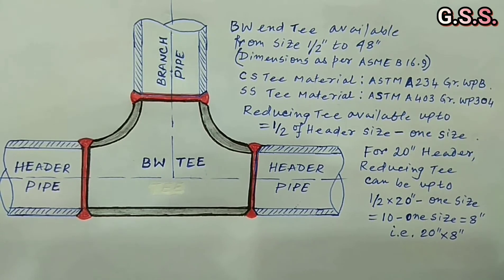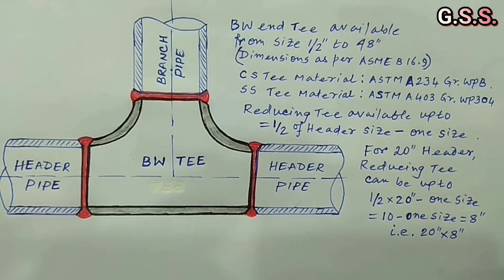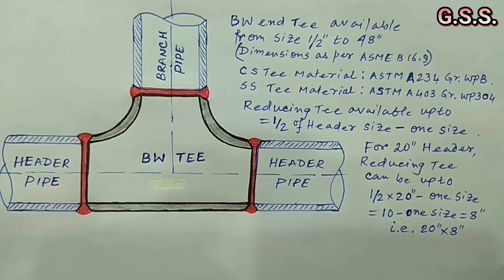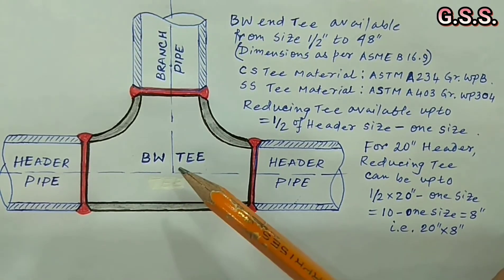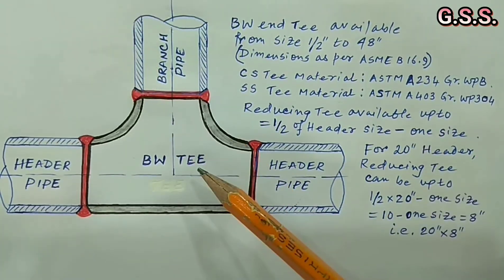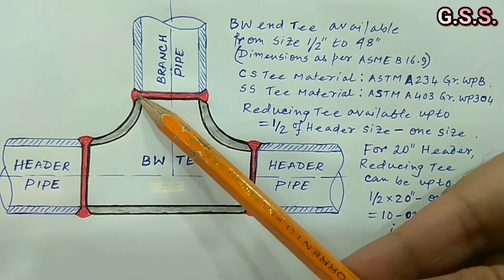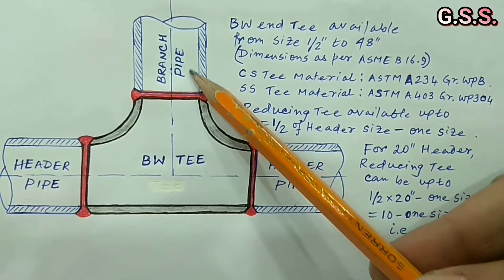If we want to have 48 inch by 16 inch branch connection and we cannot replace the T by direct branch connection, then we have to go for a T and a reducer. Say 48 inch by 24 inch T and 24 inch by 16 inch concentric reducer.